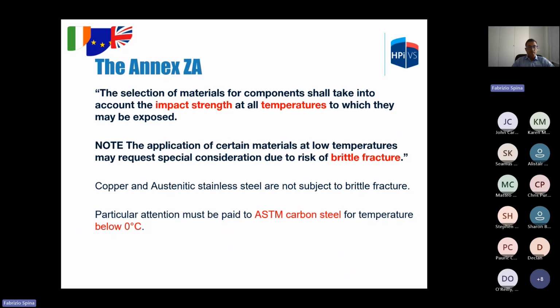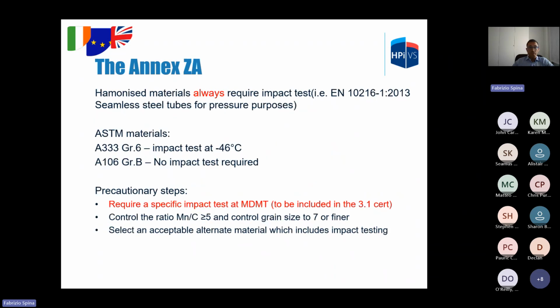Copper and austenitic stainless steel are not subject to brittle fracture. So when you use copper or austenitic stainless steel, you can ignore the impact strength and the brittle fractures, but particular attention must be paid when using ASTM carbon steel for temperatures below 0. Harmonized material, for example EN 10216, always requires impact testing.